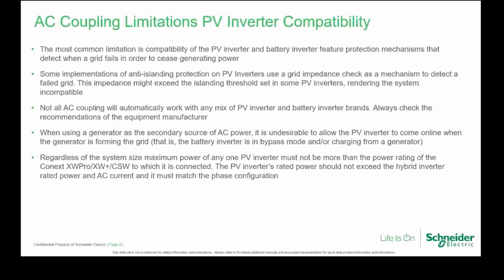When you use a generator as a secondary source of AC power, you'll make sure the PV inverter doesn't come back onto the line and back onto the generator. So you either have to bypass it or have a changeover switch so that either one or the other is on, but not both at the same time. It also means that the system size, the maximum power of any one PV inverter, must not be more than the power rating of the XW Pro or XW Plus to which it's connected. So basically, it's a one-to-one ratio for the PV inverter to the XW Plus.